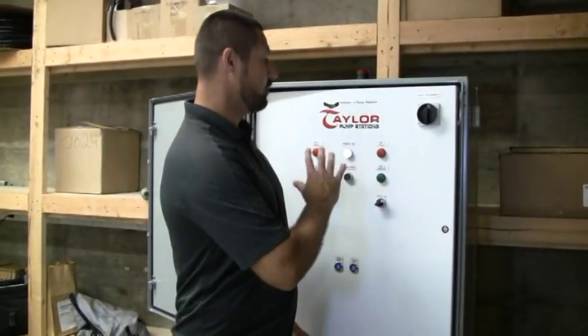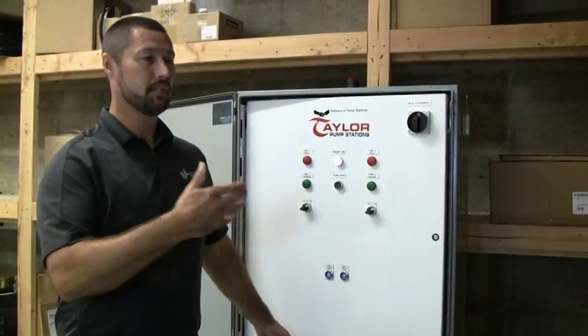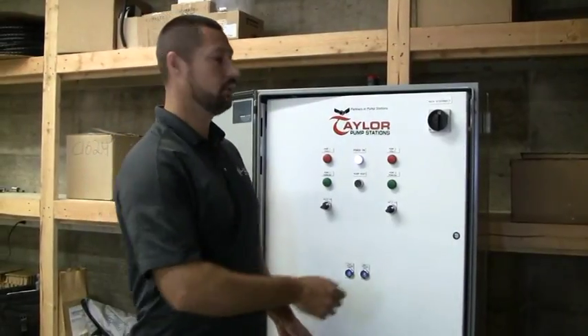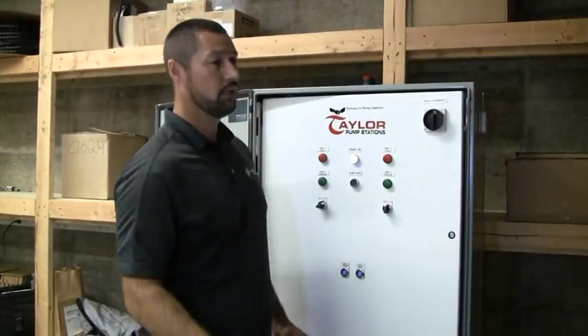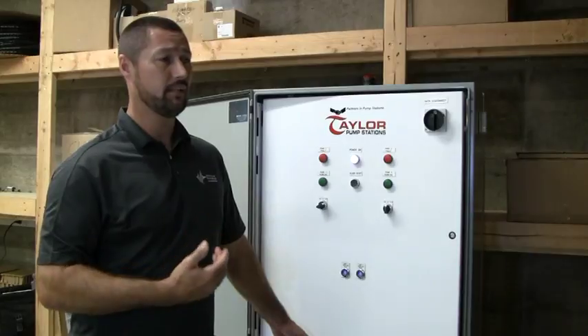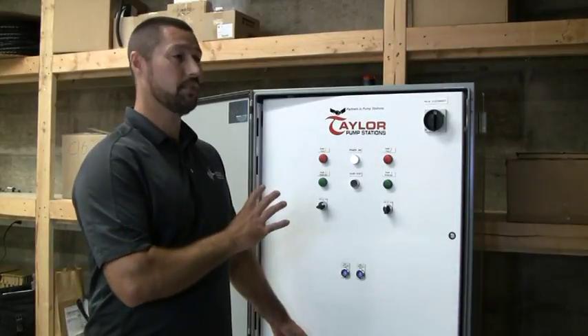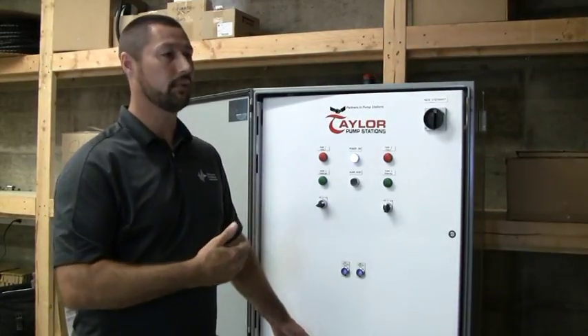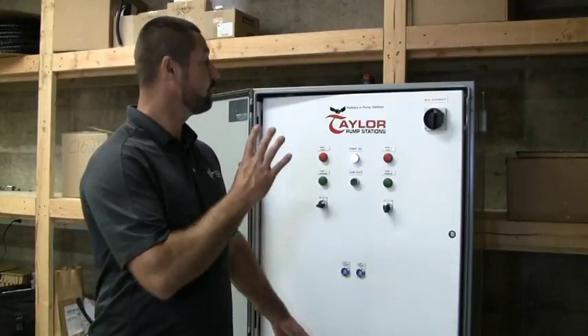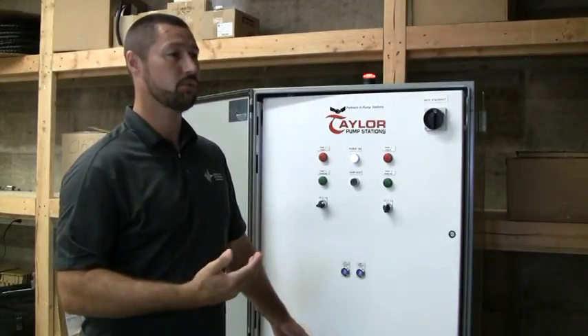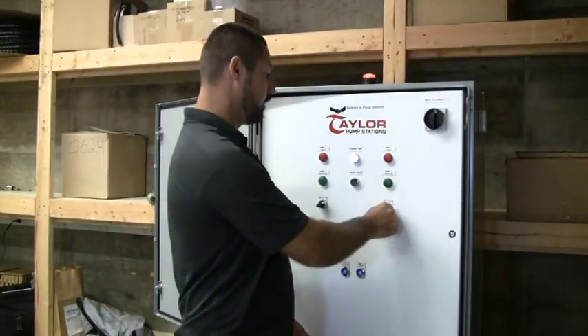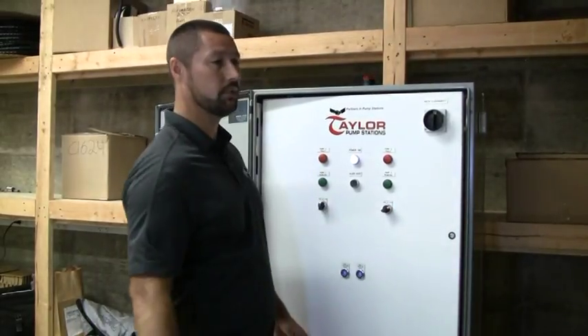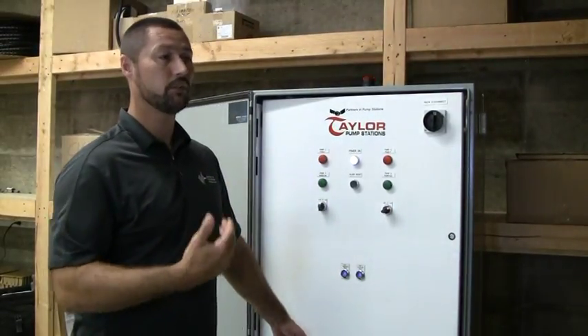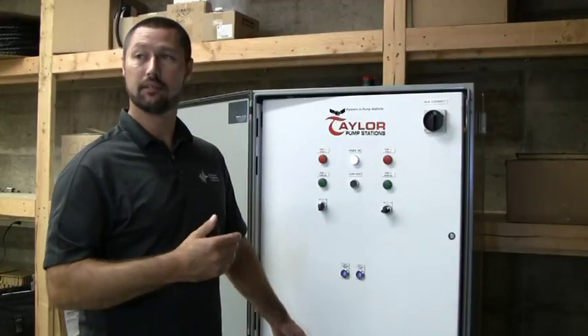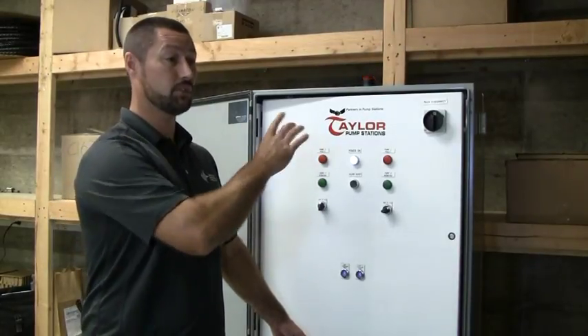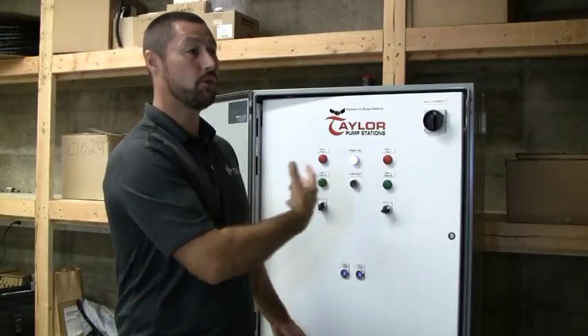So even at the low end, if somebody comes in, services it, turns off power, and they put these switches in the off position, they're going to have this local light indication saying, hey, something changed on the panel and I don't like it. So the controls are telling them that this red light indicates that something's wrong, would you please check me? Either switch. If it's not in the auto position, then the panel's going to tell you, hey, please put me back the way it is. If not, then that's okay, but just know that I myself, the panel, know that something's not right.